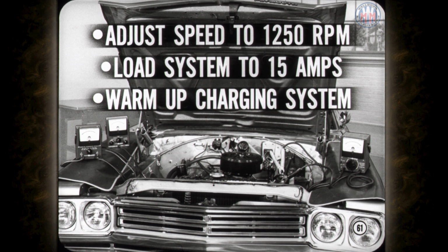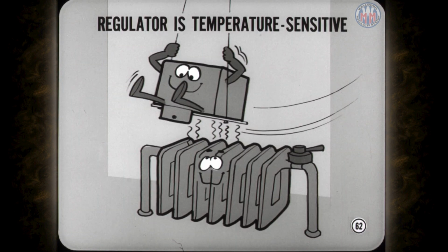Do you have to run the engine for 15 minutes like the manual specifies? Yep, you sure do. The voltage regulator was out of the circuit during the other tests, and it's relatively cold. The regulator is temperature sensitive, so the charging voltage varies during warm-up, but stabilizes at normal operating temperature.